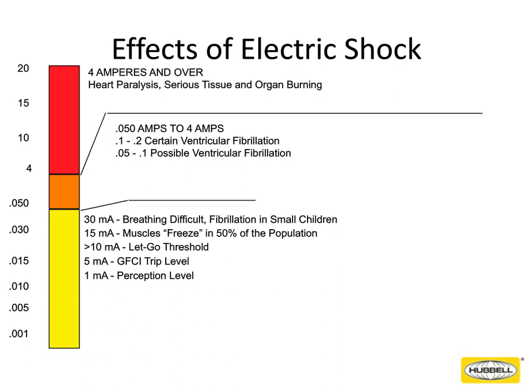Okay, when we start talking about what are the effects of an electrical shock, and again, I just want to real quickly cover how a ground fault works here and give you a basic understanding of what happens if a ground fault does exist. As you can see here in the yellow, if you have a milliamp of leakage, then you have a perception. You can feel that 1 milliamp. When you get up to 5 milliamps, which is the upper peak level where a ground fault must trip to meet UL standards, that's about 5 milliamps.